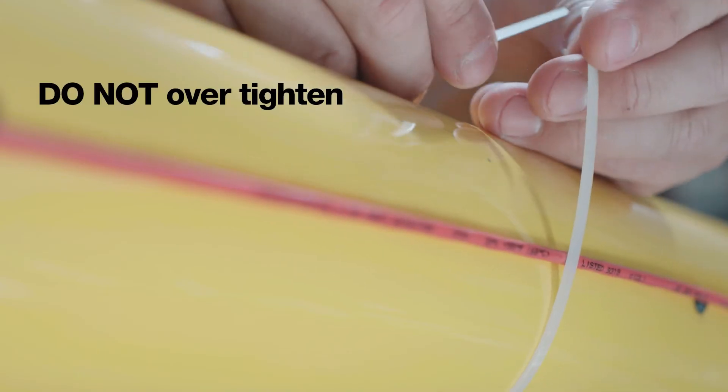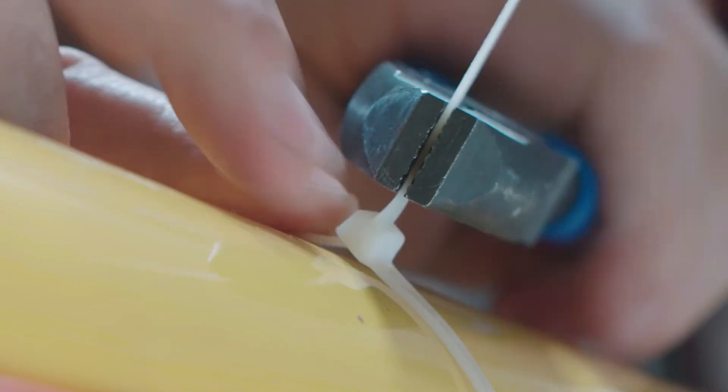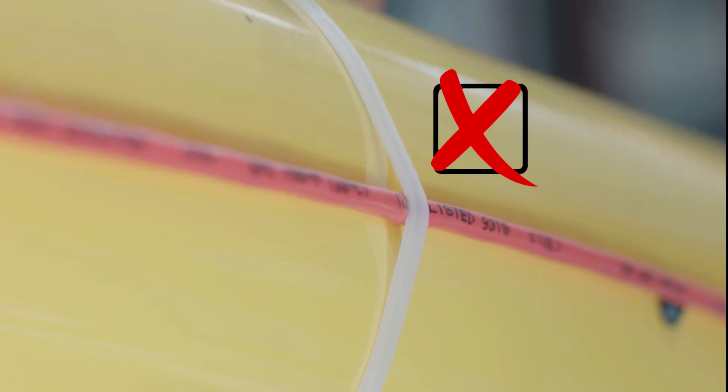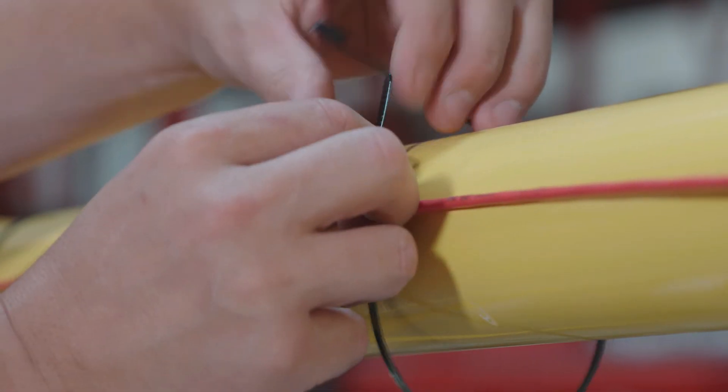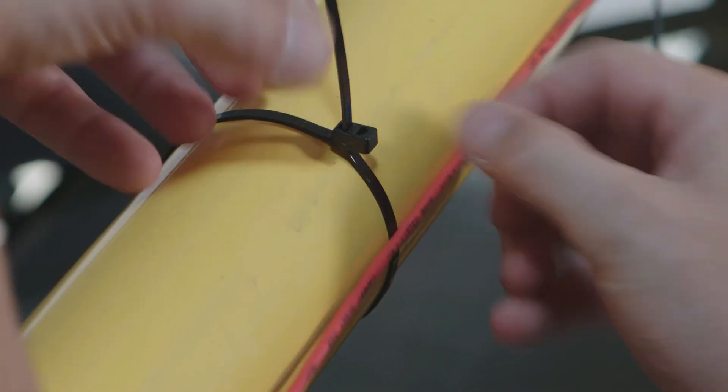Do not over-tighten the fasteners, as this may compromise the outer jacket or crush the inner insulation which may cause false alarms. All fasteners must allow the wire to expand and contract with temperature changes.